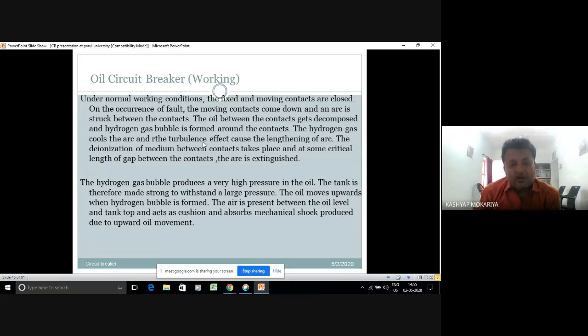Even when we were doing transformer preventive maintenance, the first step was taking a sample of oil from a drain valve and sending it to the central testing plant at that time. The BDV report arrived at the department after say 2 or 3 hours, and then we took a decision whether to filter the oil or replace it. Once after filtering the oil, if we still do not get the proper BDV, the dielectric strength of 30 kV per mm, then we take a decision of replacing the oil, and it takes time. If we take a decision on oil replacement on a transformer or a breaker in industry, it takes a huge amount of time.